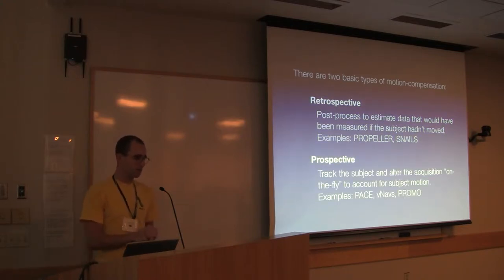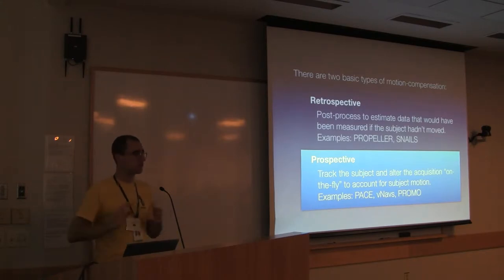The goal with prospective motion correction is that we track the subject and we change the acquisition on the fly to account for the subject motion. Instead of trying to fix bad data, the goal here is to get the right data in the first pass. But in order to do that, we have to modify the sequence dynamically. Some examples are PACE, which is a system for fMRI, VNAVs which is the system we've been developing here, and PROMO which is a similar system on the GE platform. I'm going to talk exclusively about prospective methods because that's what I do and I'm excited about.